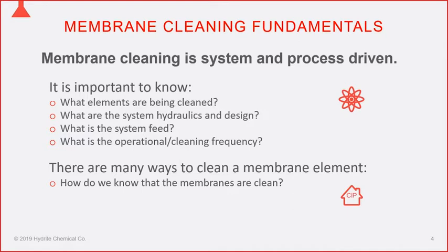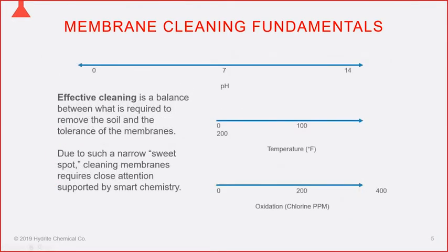More seasoned account managers will know how to look at the system hydraulics and gauge whether or not the system is functioning properly. You should be aware of your feed stream because membrane systems don't like upsets — they like consistency. Account managers should review not only CIP sheets but production sheets periodically with a membrane system.